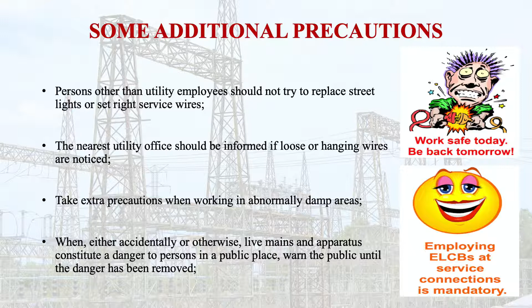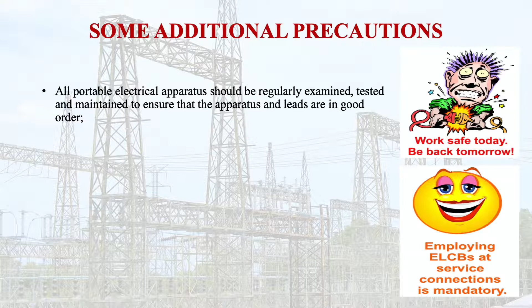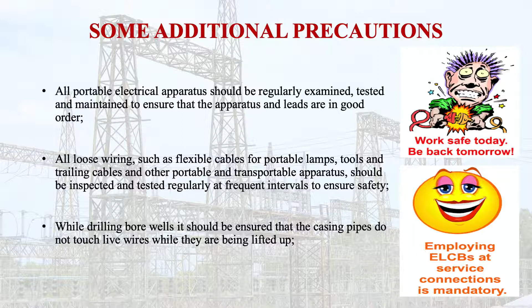All portable electrical apparatus should be regularly examined, tested and maintained to ensure that the apparatus and leads are in order. All loose wiring such as the flexible cable for portable lamps, tools and trailing cables and other portable and transportable apparatus should be inspected and tested regularly at frequent intervals to ensure safety. While drilling a borewell, it should be ensured that the casing pipe does not touch live wires while it is being lifted up.